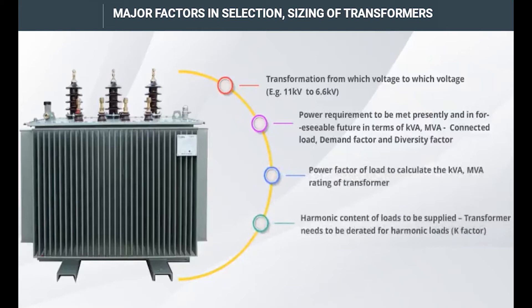Harmonic content of the loads to be supplied is another key factor. Transformers need to be derated for harmonic loads, and this is characterized by the k-factor.